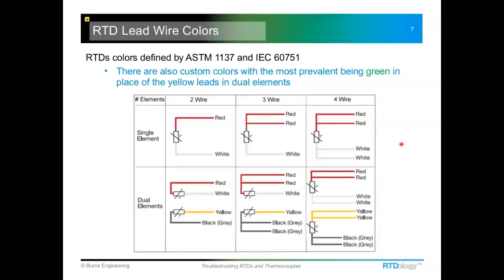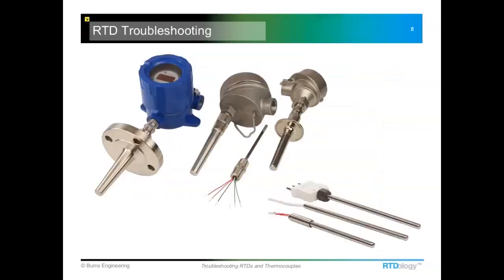One anomaly: the standards call for yellow lead wires in the case of a dual sensing element, but you'll see several manufacturers using green. That started way before either standard existed and just hasn't been changed yet. If you do have questions on RTD construction, please type them into the chat or Q&A — if you've got a question, the likelihood is somebody else has that same question.